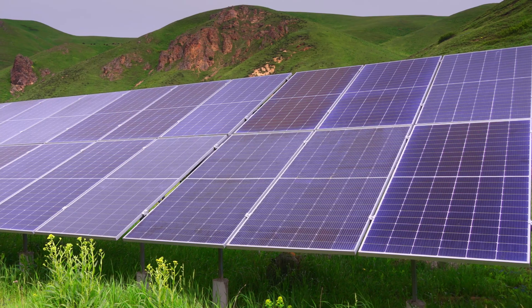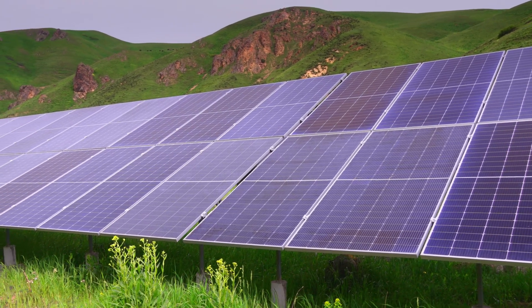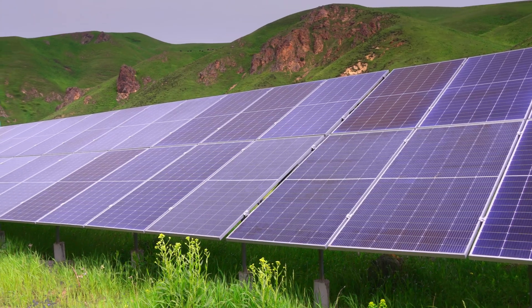What I'm about to say next typically doesn't apply to many people because of budget constraints, but it's still worth mentioning. There is such a thing as having a battery bank that is too large for the amount of panels you have. You want to make sure those batteries are getting a full charge at least every two days of full sun. I like to make sure those cells and batteries are being balanced all the time, which means they need to get a full charge, so you don't want to go weeks without having your batteries fully charged.